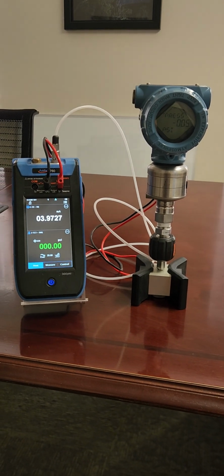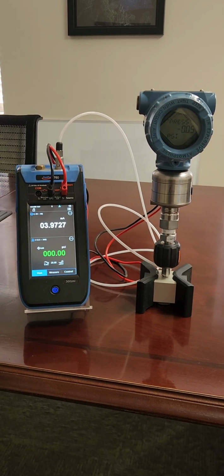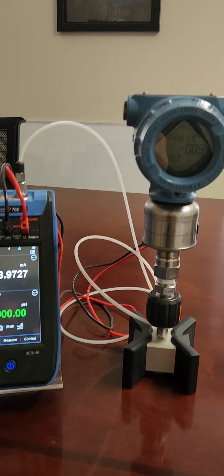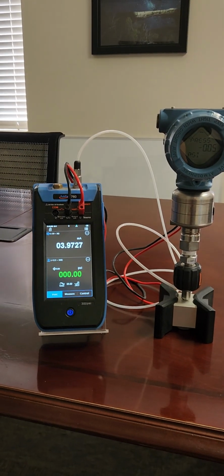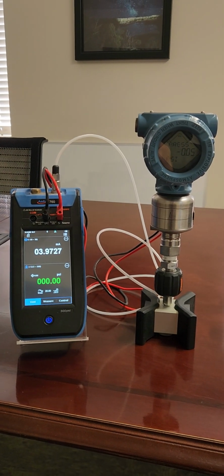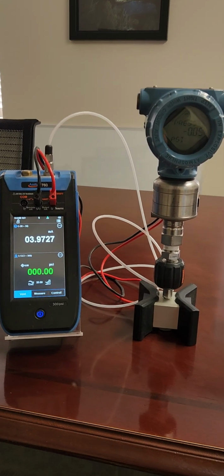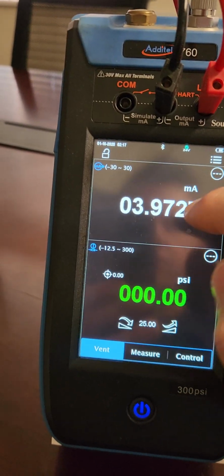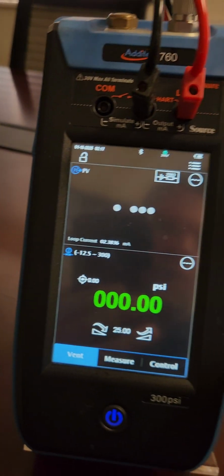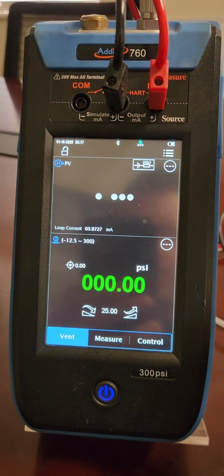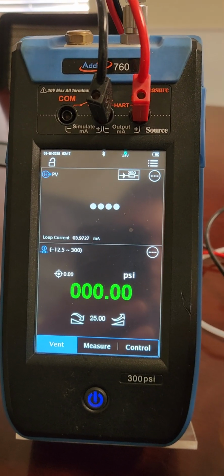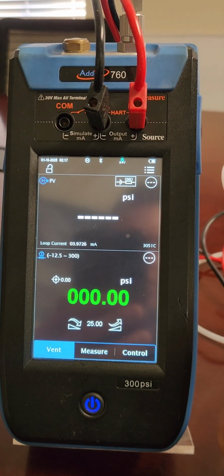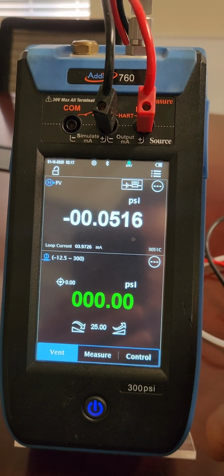All right, I'm going to show you how to use a 760 with a Hart transmitter. Here you can see I have a 760 MA hooked up to a Rosemount 3051. On the display of the 760, right now it's reading milliamps. So if I want to change it over to read Hart, I would select the menu, Hart. It has a built-in resistor, so it's able to talk to the unit, and it also does supply the 24 volts.